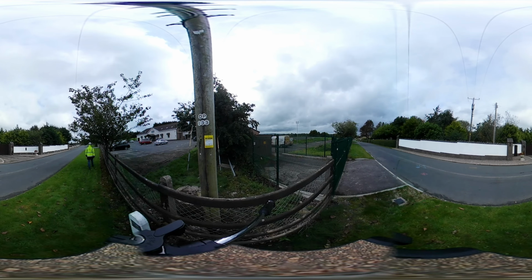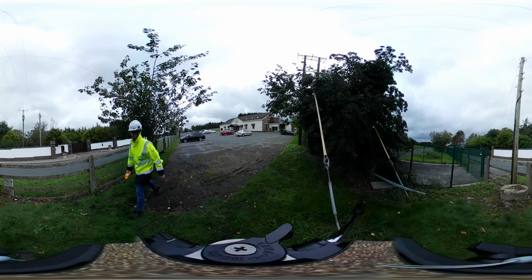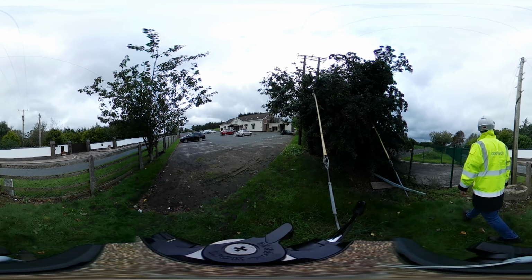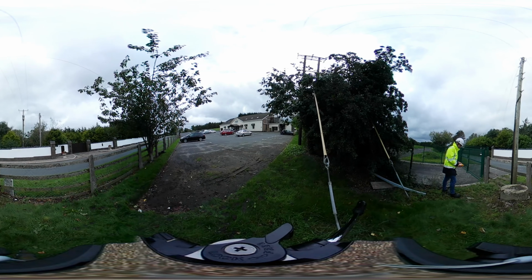One of the most important parts of the site-specific power risk assessment is determining the height of the overhead conductors and the height of the open reach pole above ground. In order to figure out the height of the overhead conductors, we use an ultrasonic non-contact measuring device. Set the device on level ground and measure twice.